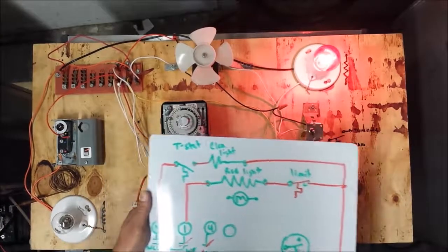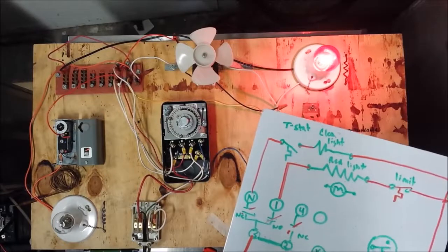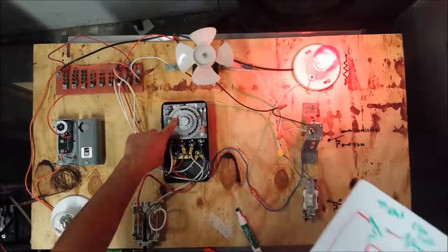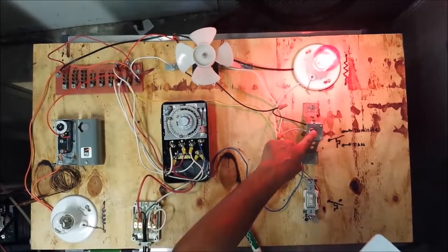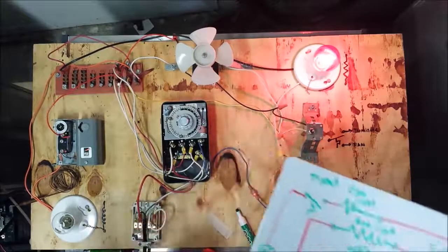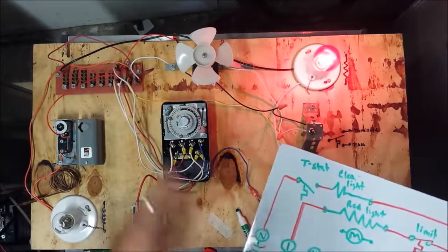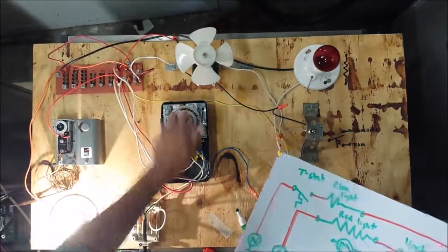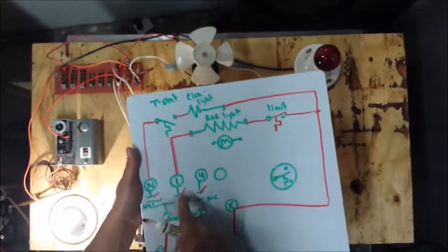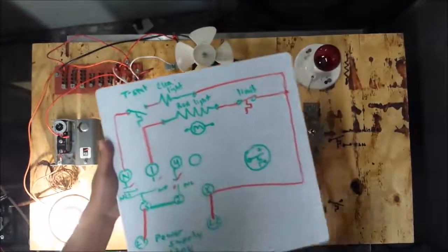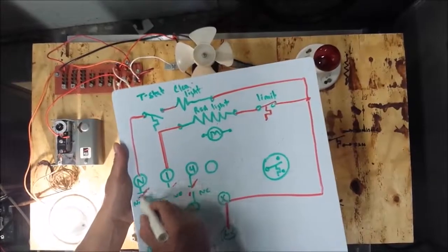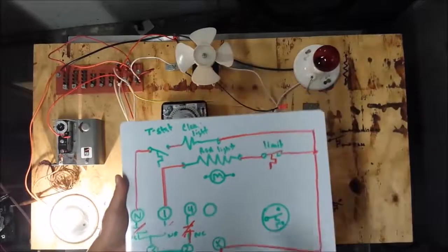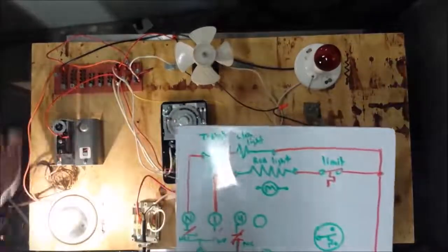Okay? So once the defrost has completed, either by time duration in the middle or by our defrost terminator, then defrost will end. So we're going to advance this. It's just based on our timer. So we're going to turn this, kick it out of defrost, and now our defrost terminals have opened back up, and our normally closed switches have reclosed. Okay. Since now this is back on, we're back into normal freeze mode.